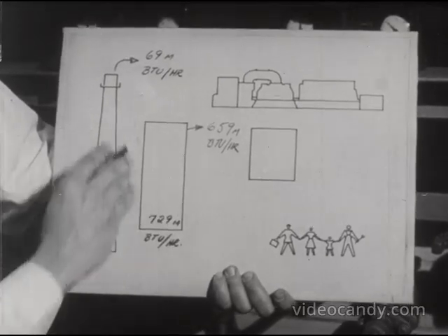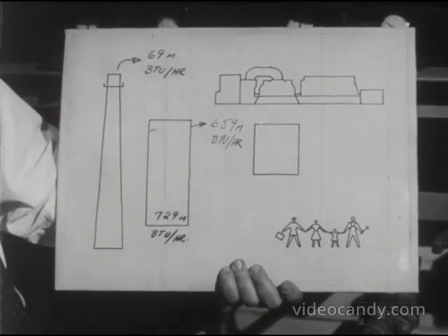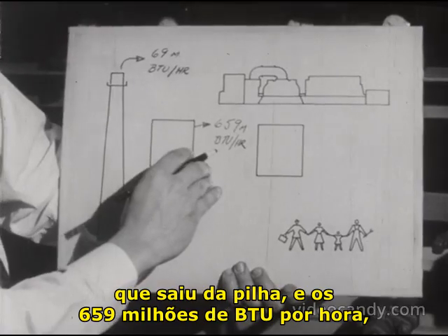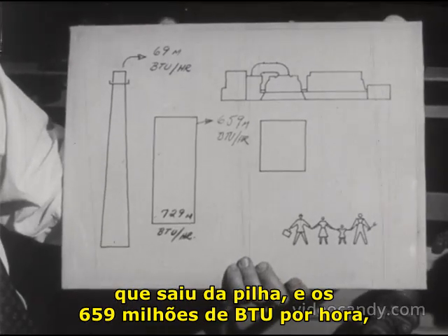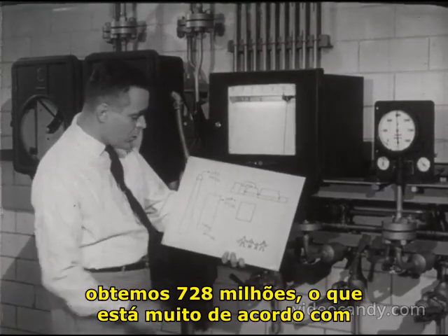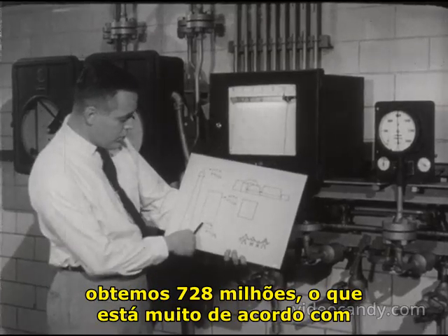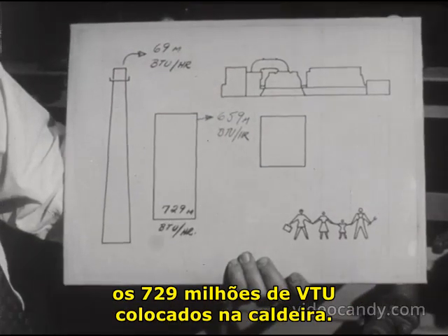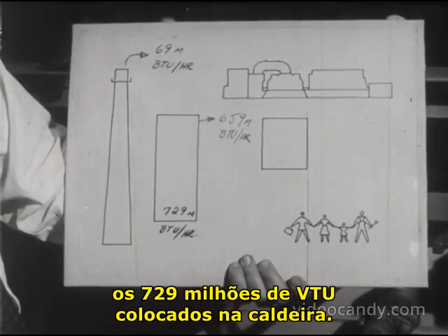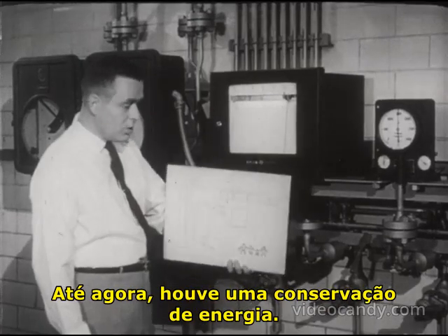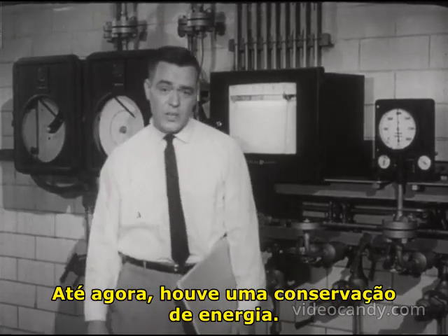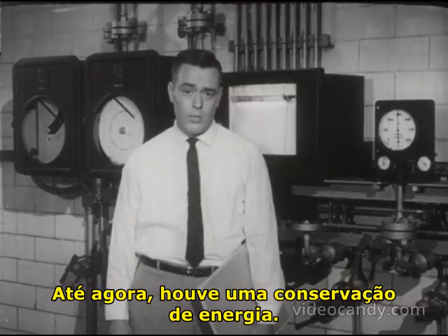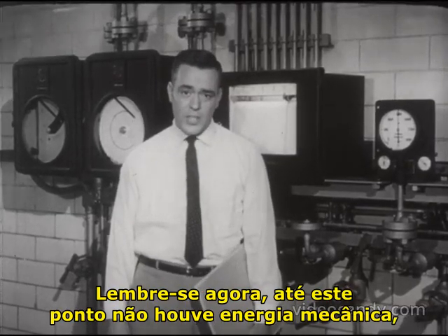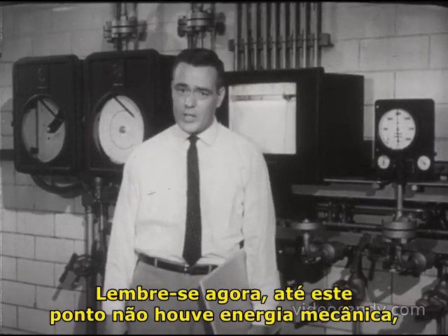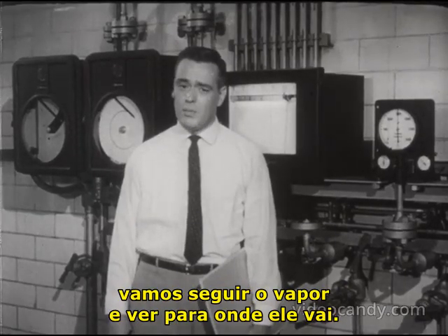By adding up 69 million BTU per hour that went out of the stack and the 659 million BTU per hour, we get 728 million, which agrees very closely with the 729 million BTU put into the boiler. So far, there's been a conservation of energy. Remember now, up to this point, there has been no mechanical energy. Let's follow the steam and see where it goes.